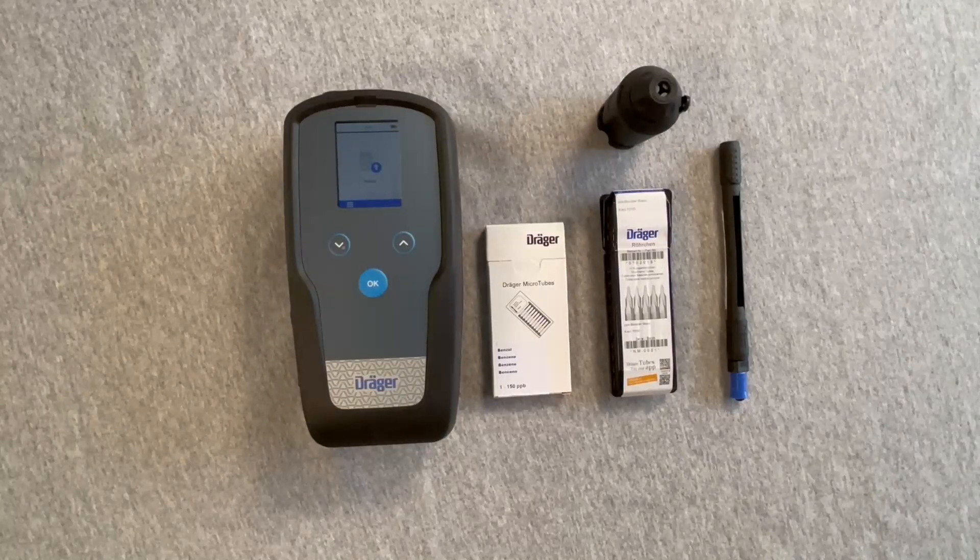The Dräger X-am 7000 with the Parts Per Billion Booster Tube. The Parts Per Billion, or PPB, Booster Tube is used to improve the sensitivity and selectivity for some microtubes. Presently it is used with the 1 to 150 ppb benzene and 25 to 500 ppb 1,3-butadiene microtubes.